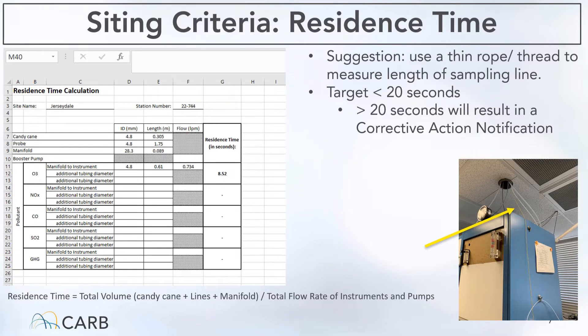One thing to note about this calculation: it represents the residence time of the air mass from the candy cane inlet to the bulkhead of the inlet of the analyzers, meaning it does not include the internal sampling train of your analyzers. So that's one thing to note about calculating this residence time.